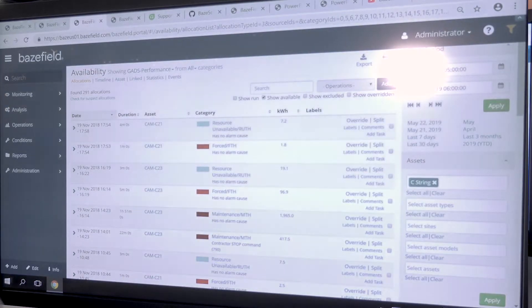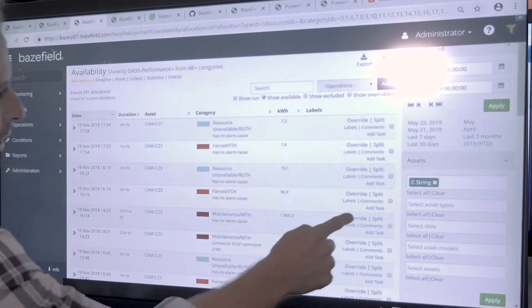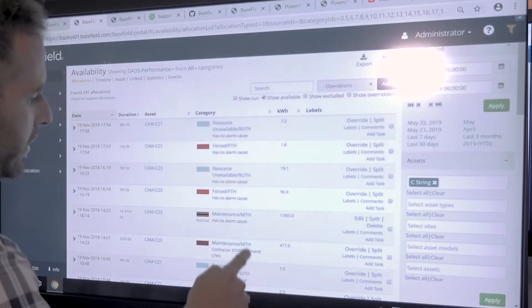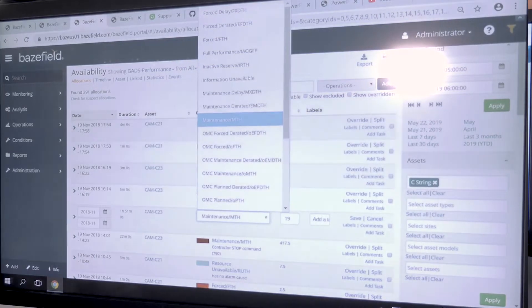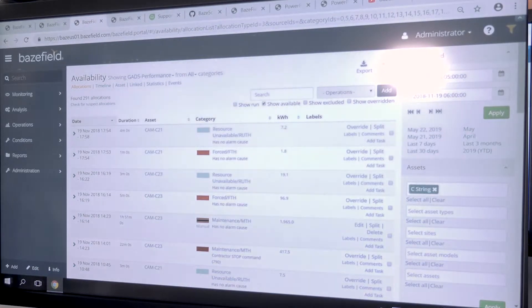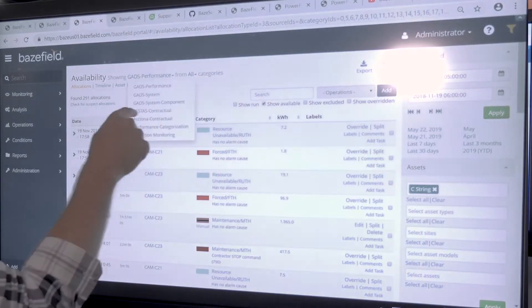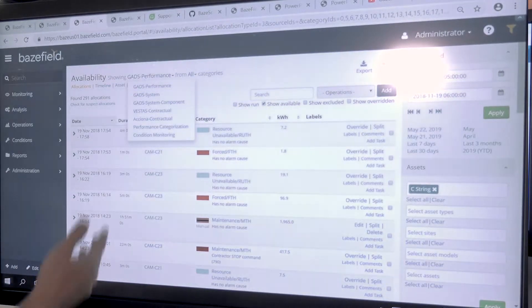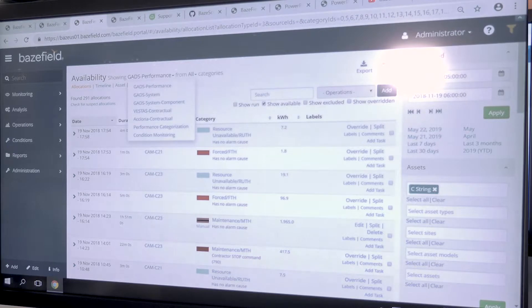If you're unfamiliar with the availability tool, we have a complete demo on our YouTube page. Briefly, you're allowed to change classifications — if the Bazefield system didn't get the correct classification on your outage, you can click 'override and edit' to change it. You can use as many different classification systems as you want. For wind and solar, we use GADS and IEC conventions to map all OEMs and inverter types to one uniform standard, and you can navigate between the different classification systems. You might classify downtime to a GADS convention, an IEC convention, and maybe a contractual convention specific to your OEM like Vestas or Acciona.